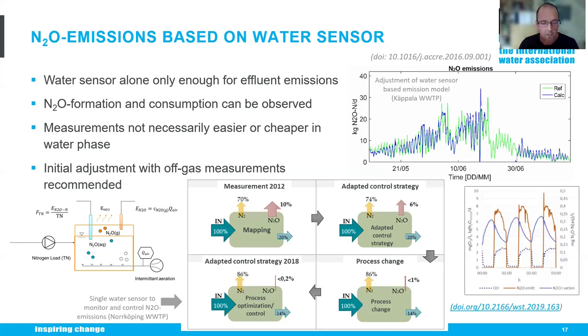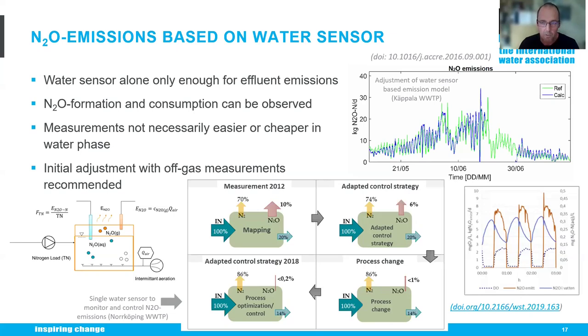If you use the water sensor and want to quantify actual emissions with a mass transfer model, our experience is that you need to adjust the water sensor and mass transfer model with help of off-gas measurements. One example at a Swedish treatment plant shows the predicted emission based on the water sensor compared to actual observed emissions with quite a good fit. Another example shows one water sensor controlling emissions for a whole process, which then allowed mitigation of those emissions. If you apply the water sensor correctly and adjust the sensor and mass transfer model, you can use these sensors quite efficiently.